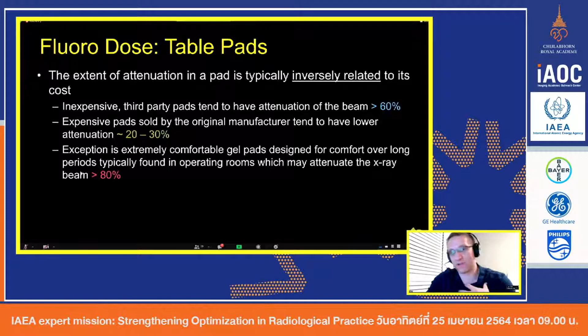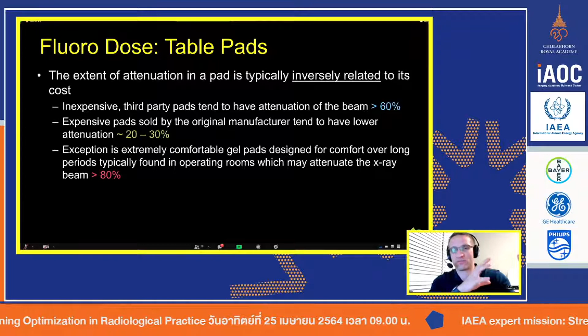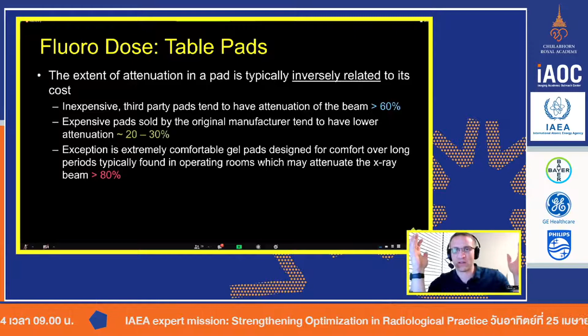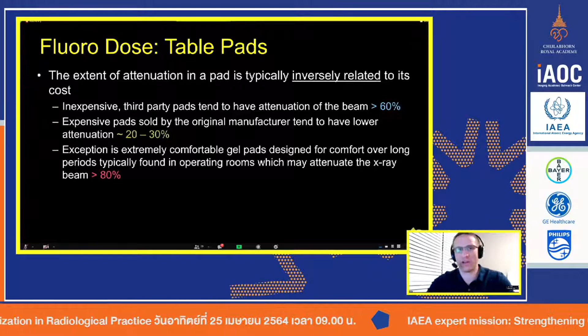And one of the things that, as a medical physicist, I like to do, for example, we've just added a small part, we added a building to our hospital. So we've increased the number of beds we have in our hospital. And the hospital went out and bought all the new hospital beds and all these pads. And of course, they're looking at the most comfortable pads, the pads that hopefully reduce all of the bed sores and all of these things. They didn't think one little bit about radiation. And so when we found out what they bought, we did some measurements and I showed them that they've in effect increased the dose to all of our patients by 30 to 40% if we have to image using those pads. So just be careful of what pad you put, especially on the fluoro tables.